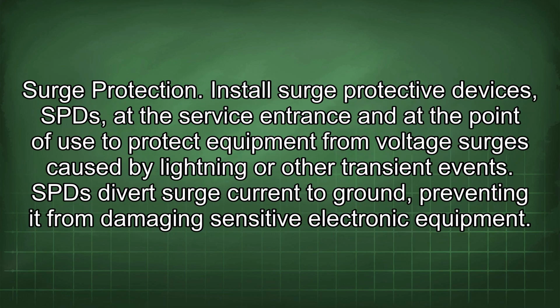Surge protection. Install surge protective devices, SPDs, at the service entrance and at the point of use to protect equipment from voltage surges caused by lightning or other transient events. SPD diverts surge current to ground, preventing it from damaging sensitive electronic equipment.